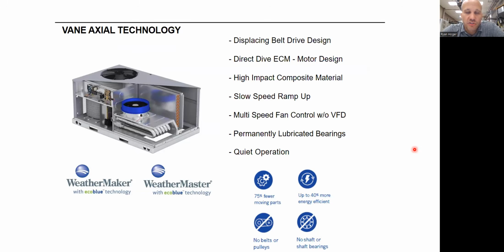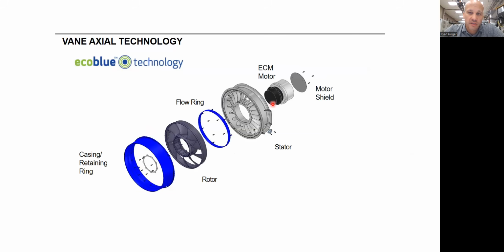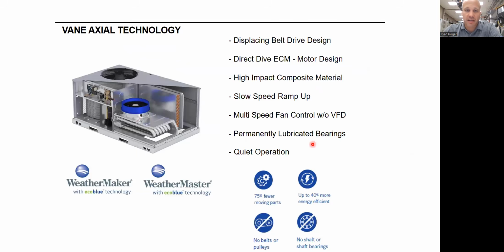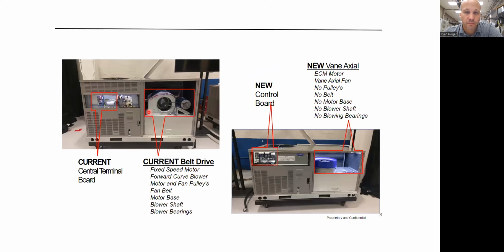As I mentioned, there's ways to do this now that are direct coupled that don't involve the belts, but still get a high amount of torque. So one of those is vane axial fans. And there's a whole blow up of it, which is a whole other description in itself. But what that guy is doing is once again sucking air through this cooling coil, but in this case, it's sucking it down through this fan, through the heat exchanger into this space. And this particular fan design is a little bit unique in that regard. Only some manufacturers have something like this right now, at least on this size equipment.